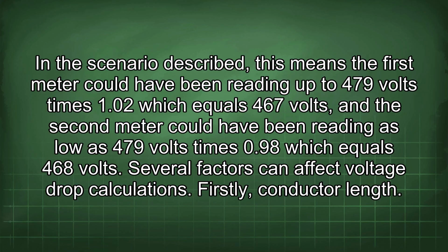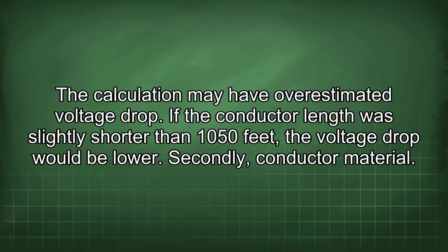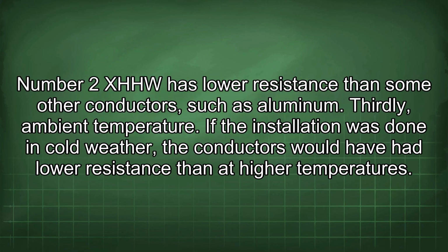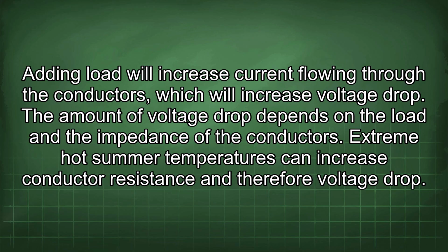Firstly, conductor length. The calculation may have overestimated voltage drop. If the conductor length was slightly shorter than 1050 feet, the voltage drop would be lower. Secondly, conductor material. Number 2 XHHW has lower resistance than some other conductors, such as aluminum. Thirdly, ambient temperature. If the installation was done in cold weather, the conductors would have had lower resistance than at higher temperatures. Adding load will increase current flowing through the conductors, which will increase voltage drop.